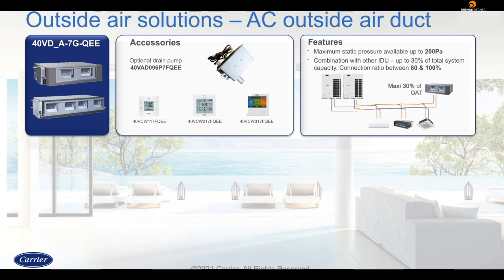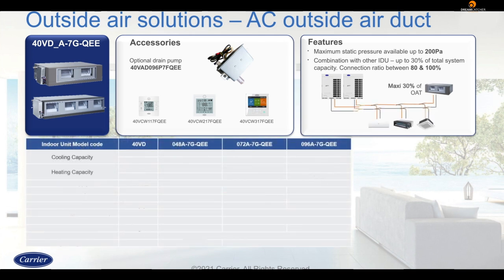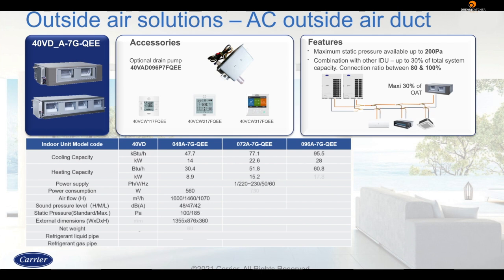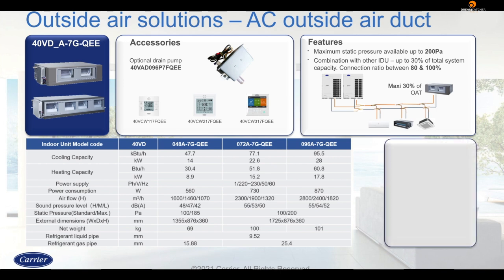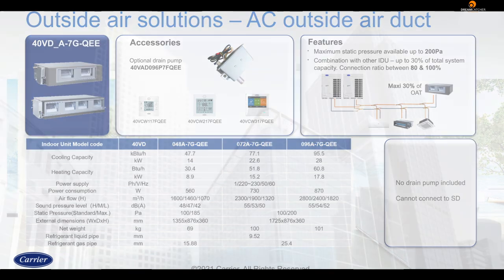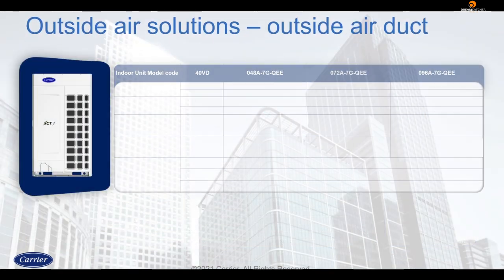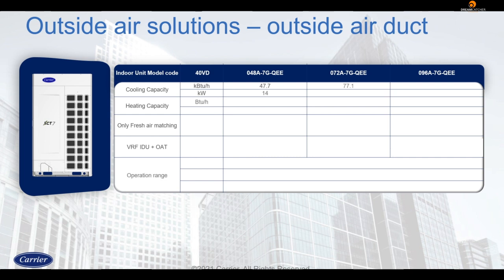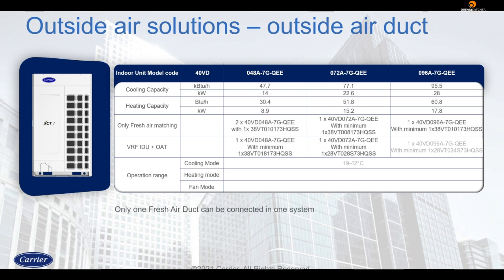It offers a cooling capacity of 47.7, 77.1 and 95.5 kBTU per hour. It can be connected to VRF outdoor units in 1-to-1 connection or connected with other VRF indoor units, but cooling capacity cannot exceed 30% of total system capacity. Please note that the combination ratio for the unit is only 80 to 100%, so it needs to be kept in mind while designing the system. Another thing to note is that it cannot be connected with a side discharge system. Here are some rules that you need to follow to design a system with an outside air duct. Keep in mind that only 1 duct fresh air can be connected in one system.